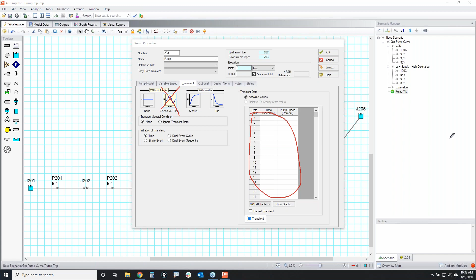Well, AFT Impulse is all about transients. So if you go to the transient tab, this is where you pick which type of transient you want to work with. So a without-inertia model is very simple. If I was to choose speed versus time, all I would be doing is specifying how the speed of the pump changes over a time profile. It's not accounting for any of the inertial effects on the pump, the fluid, or the motor. And it is important to account for those.